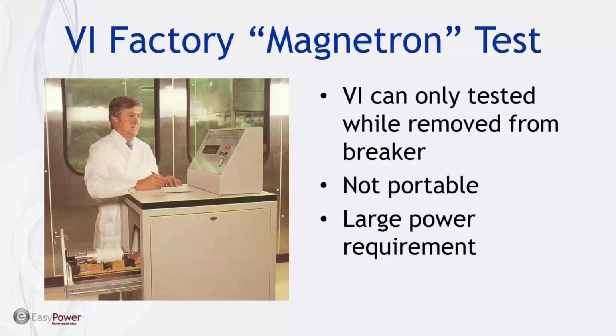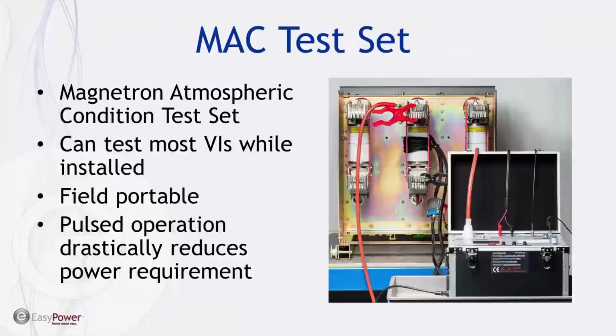So we, in 2011, began to develop a portable test set for doing this magnetron test, and the name we came up with was Magnetron Atmospheric Condition Test Set, or MAC test for short. So our MAC tester can test vacuum interrupters while they're still installed in the circuit breaker because of our special coils that we developed for supplying that magnetic field. It's very portable. The test set itself weighs about 50 pounds.